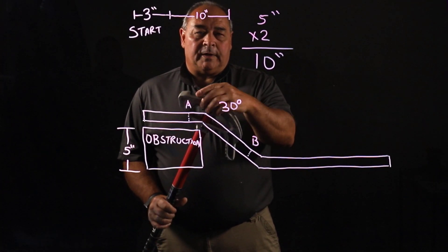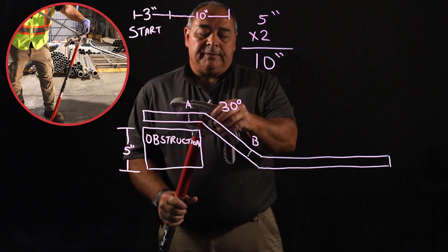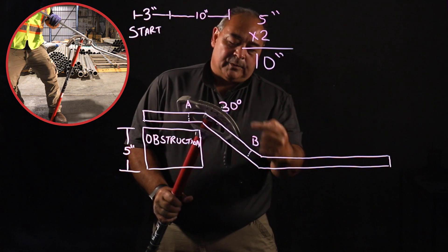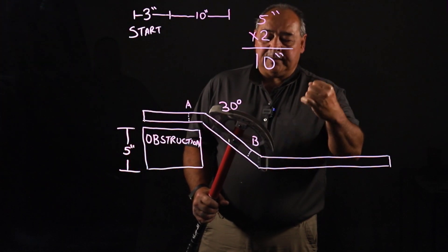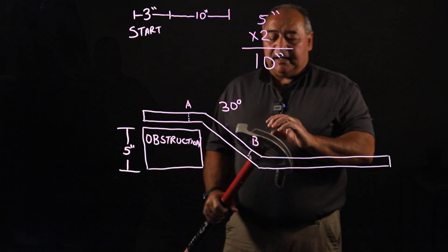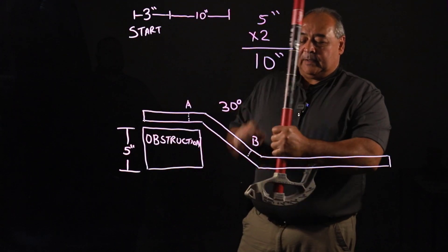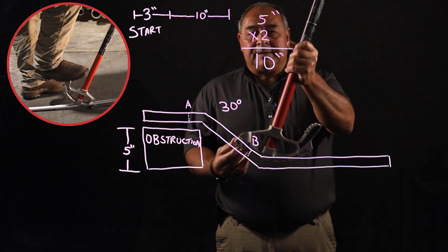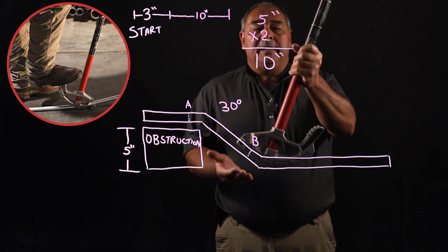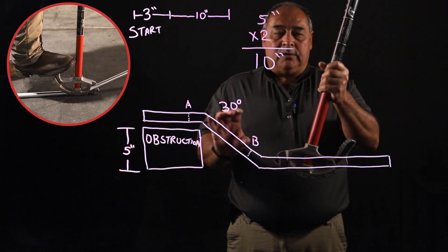You would bend this to 30 degrees going this way. Then you just spin the pipe around and slide it through. And what it ends up being, it changes the orientation to the bender being like this. And then you would bend the second bend at 30 degrees, and it will equal an offset.